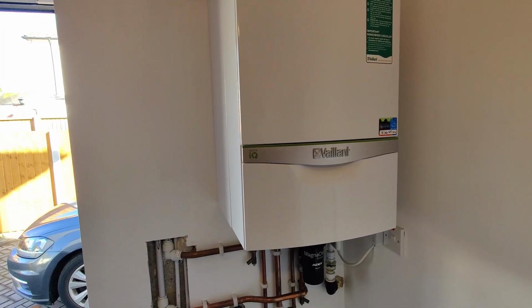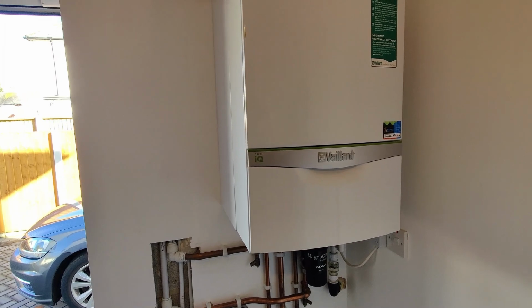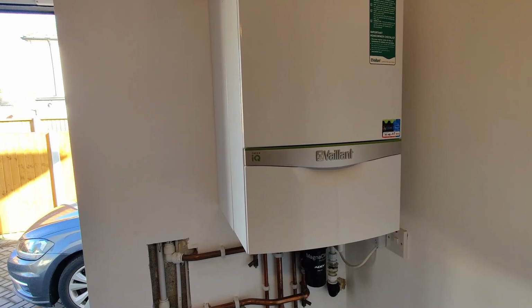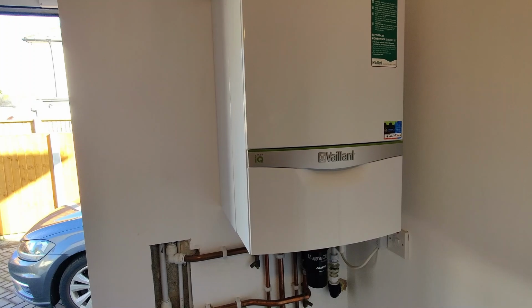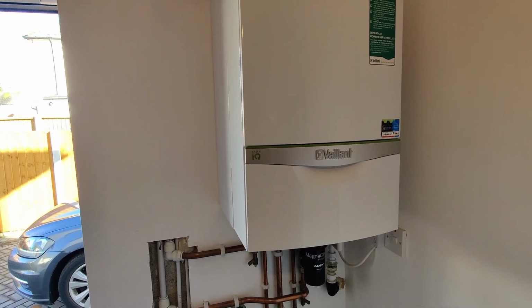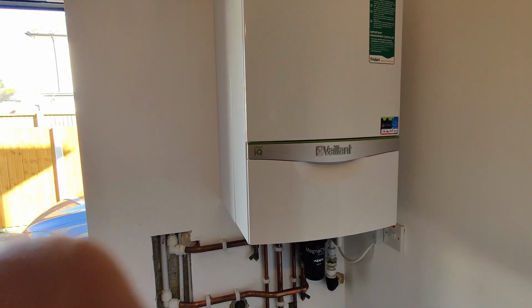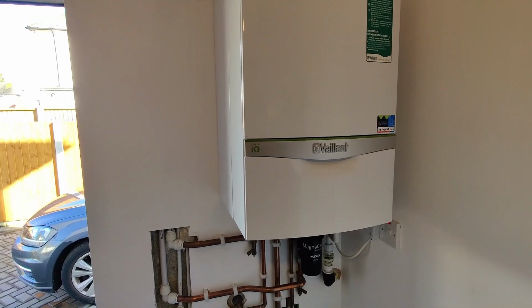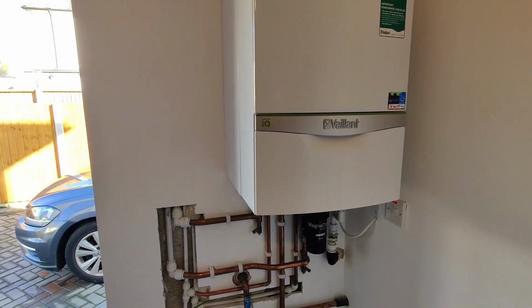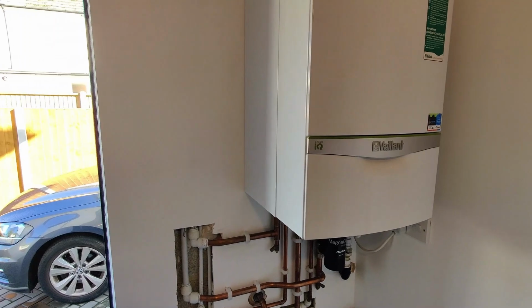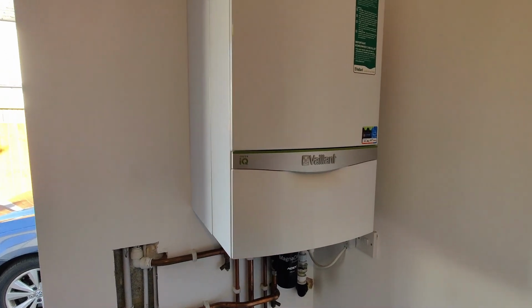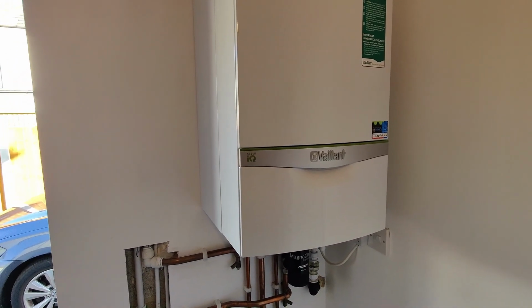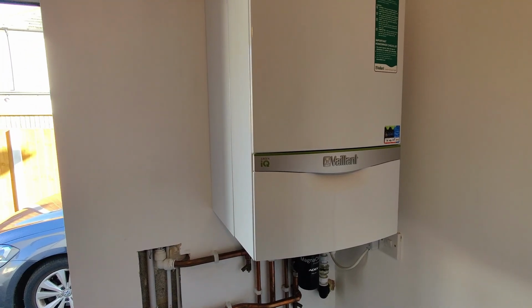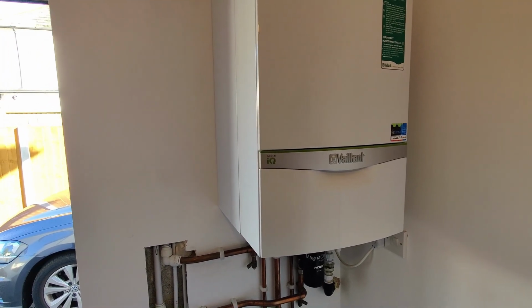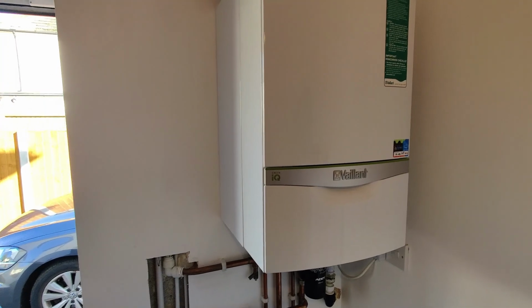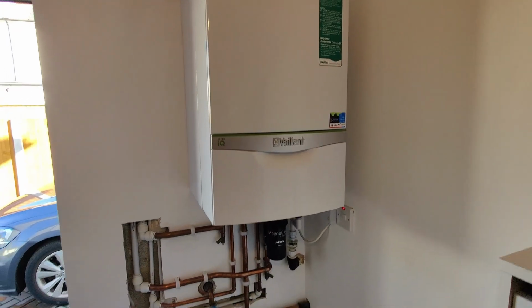We'll possibly look at that when the combustion readings go a bit down, or on the third or fourth inspection and service, and then going forward do it regularly every year. So that's all good. The water quality is great, so I didn't bother with the water sensor on it, because normally on an older boiler, on every service I open the sensor up as a habit and clean it. On this one everything is spot on, working great, so there was no need to do that.